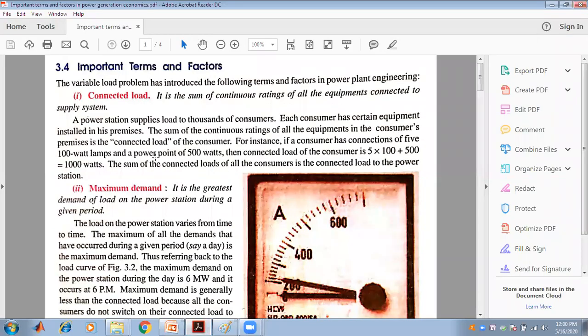The first factor is connected load. The connected load is the sum of the continuous ratings of all the equipment in the consumer's premises. For example, if a consumer has connections of five 100-watt lamps and a power point of 500 watts, the total connected load is 1000 watts. The sum of connected loads of all consumers is the connected load to the power station.